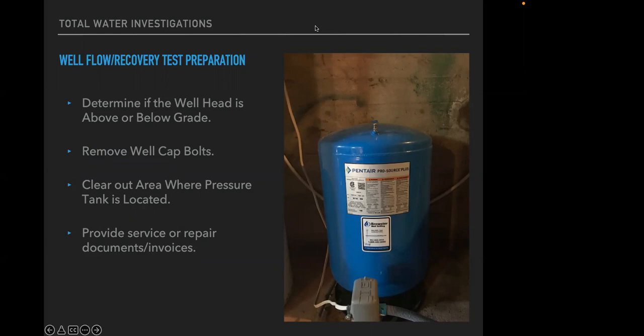I've done a bit of electrical work over the years, and one thing with that well pump overheating, I was just curious whether it overheated and had a breaker in the actual pump or whether it was blowing the breaker in the house. Because if it was the breaker in the house, it's possible that the power supply, the wiring to the pump, may not have been adequate, and it might just be blowing breakers. It could be an electrical issue, not the actual pump.